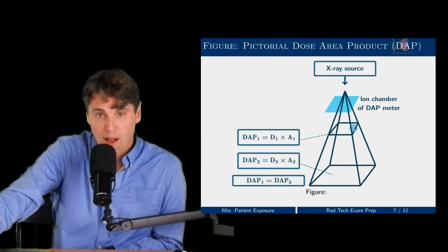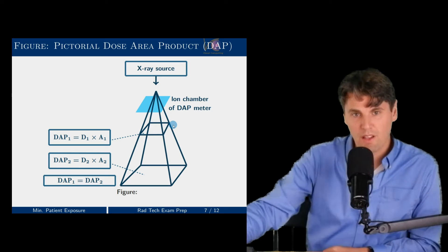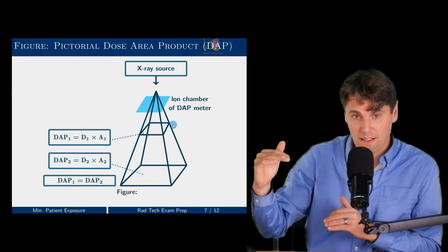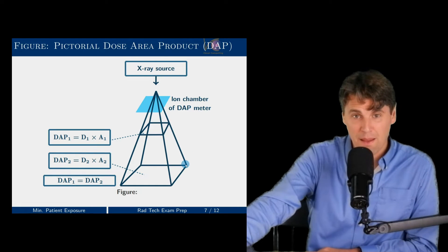If you looked at the dose area product in this rectangle right here, the rectangle is smaller, but the relative exposure is higher than as you come down here because of our one over R squared. If you measure the dose area product at any given distances from our x-ray tube, you're actually going to come up with the same measurements.